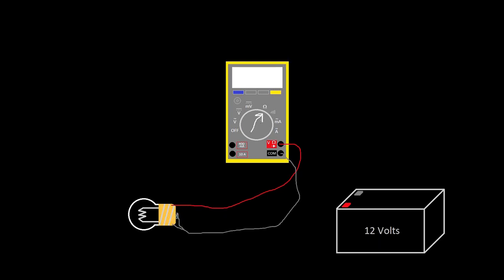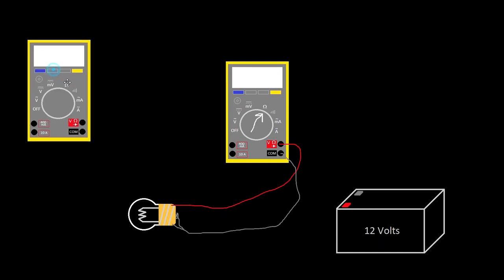So we're going to set it to resistance, and there's something I want to discuss about what happens when your meter is set to resistance. I mentioned before that I always check the voltage of a circuit before I check resistance, if I don't know what's on it. In this case, it's a light bulb that we can all clearly see is not hooked up, so we're not worried about it. But let's imagine it's just a pair of wires that you removed off a panel, or you're in a junction box, and you're not 100% sure what's on it. I would always meter for voltage first, just to make sure that there's no voltage on it.